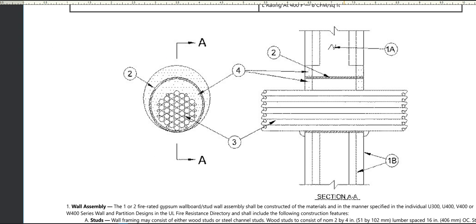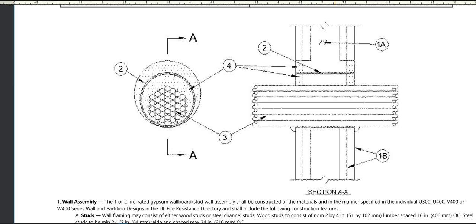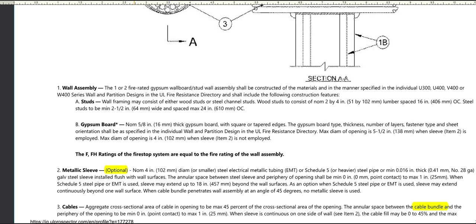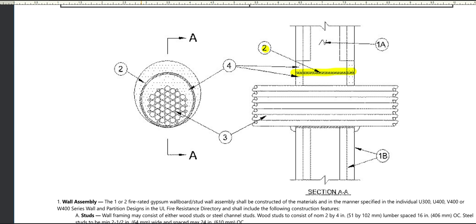Now I find a drawing. Please remember that the drawing provided by the laboratory is just an example — it's not to scale and does not show every single condition available. The words in the listing always trump the drawing, photo, or any sketch. For example, number two shows a sleeve going through a wall, but when I go down to item two in the text, it says 'optional' — meaning I don't have to have a sleeve. So I have sheetrock, cables going through a wall, maybe a sleeve and some sealant, but nothing required in the stud cavity.